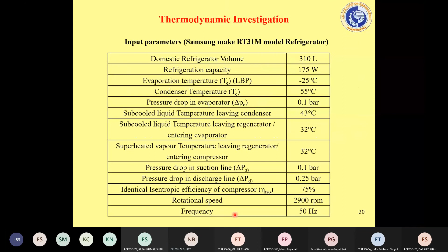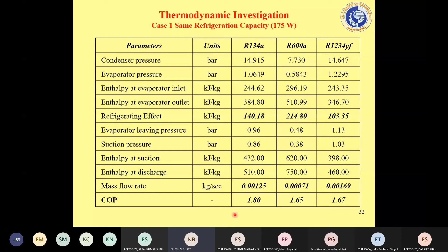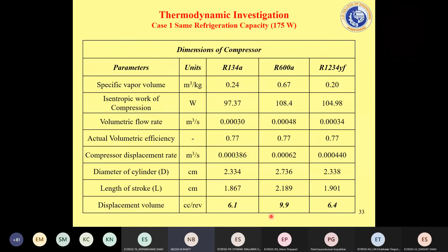Of course, the original dimension is 6.2 cc. This is thermodynamic analysis, so some loss would be there in actual calculation. So the actual compressor has a capacity of 6.2 cc. And what is required for YF is slightly higher. So these two numbers will tell you that retrofitting is possible, while this number tells you that you have to entirely change the compressor, not only the oil. Now what if you are using the same compressor?